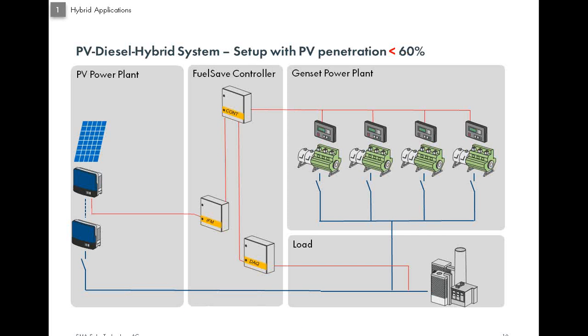However, if you want to go to higher PV penetration, and if you want to have, say, up to 60% PV, which is 60% of the genset capacity, then you need SMA's FuelSave Controller, because otherwise the system will be too dynamic, and you require these boxes which are intelligent. You require these microcontroller-fitted boxes to help ensure that your system is running smoothly and takes care of the load in all circumstances.